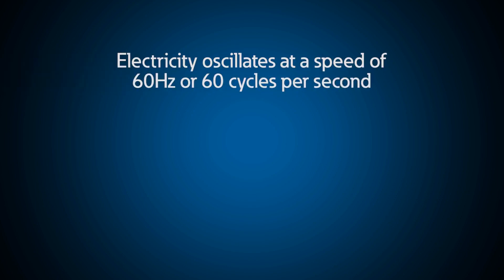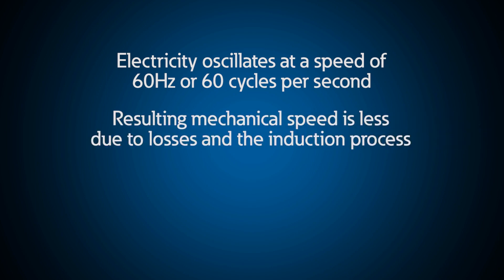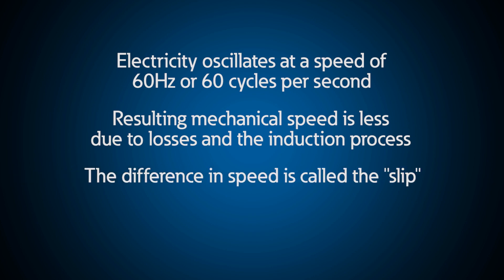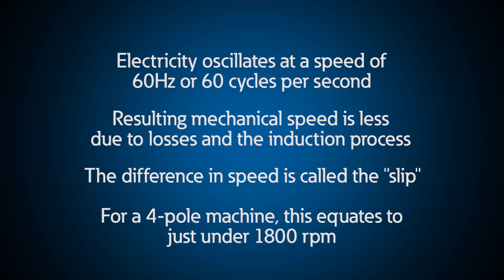The electricity is oscillating at a speed of 60 Hz or 60 cycles per second when it energizes the stator. The resulting mechanical speed of the rotor is a little less due to losses and the induction process, and the difference in speed is called the slip. For a four-pole machine, this equates to just under 1800 revolutions per minute.